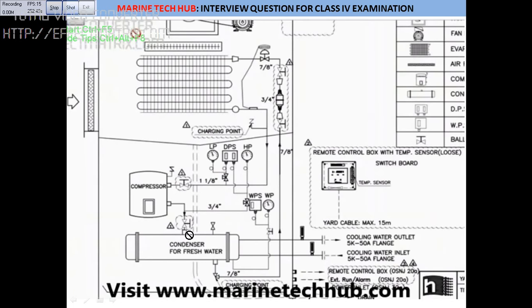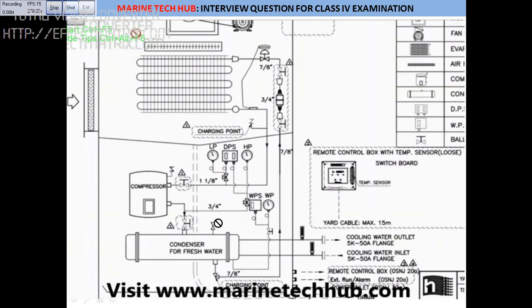Once the gas is compressed, it collects in the condenser in liquid form — you can check the level through the sight glass. For charging gas: if you want to charge very quickly, you charge liquid, not gas. However, do not charge liquid at the suction/discharge side of the compressor, as it will go to the compressor and damage it. Always charge liquid at the designated charging point after the condenser, where the liquid will expand properly.